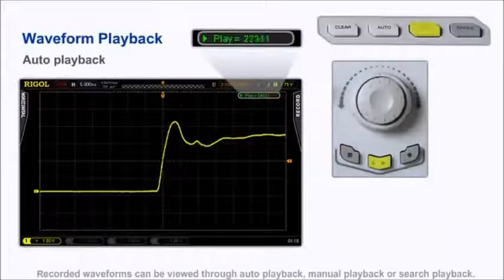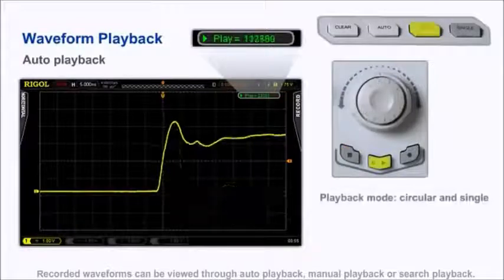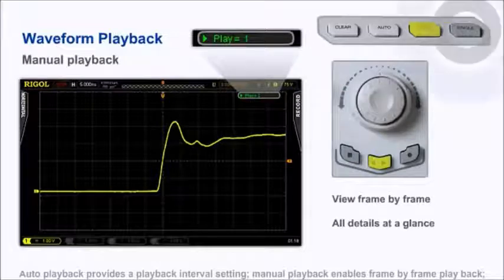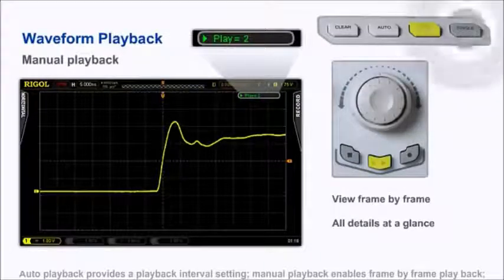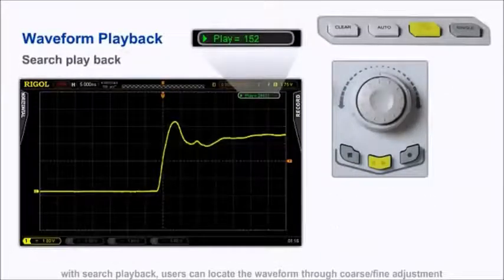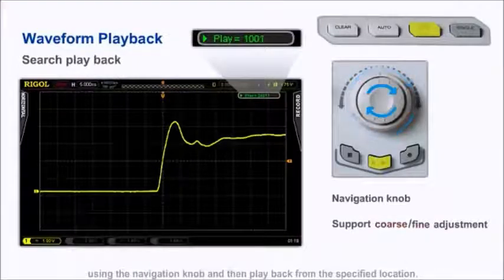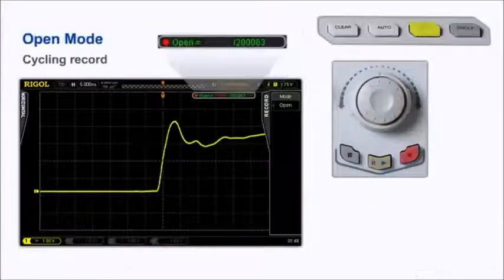Recorded waveforms can be viewed through auto playback, manual playback, or search playback modes. Auto playback provides a playback interval setting, where manual playback enables frame-by-frame playback. With search playback, users can locate waveforms through coarse and fine adjustments using the navigation knob, and then playback from that specified location in memory.